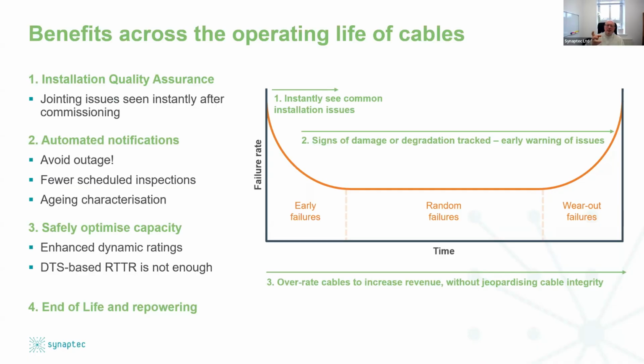And if you're always watching the cable and you're always able to run a calculation that gives you a health index and an aging effect score, you know towards the end of the life what state your asset is in and what it's worth. And you can make more informed end of life decisions as an asset management function based on data rather than offline spreadsheet based projections, which are probably less reliable, because you've got this data history building and building, showing how that asset is trending towards its end of life. Is it on schedule or better than or worse than what you intended? You'll know. So this is about informing decisions and giving confidence that you can see problems happening.